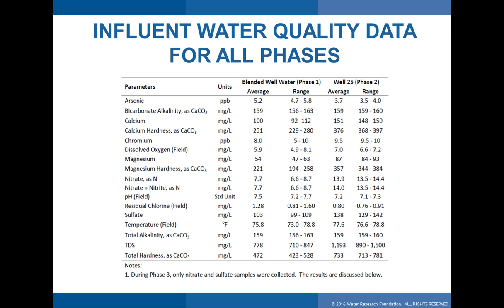We wanted to test wells with different water quality and other parameters. There's particular interest in co-occurrence and co-removal of chromium, given chromium regulations and its status as a regulated hazardous waste — the aquifer in the area seems to have a lot of it. There's also a little arsenic, so arsenic accumulation was of interest. Looking at the nitrate data, nitrates vary from 6.6 to 8.7 mg/L in the blended water and up to 13.5 to 14 mg/L. The intent is to keep nitrates below 8, so as they climb between 10 and 15, treatment will soon be needed at the Coldwater site.